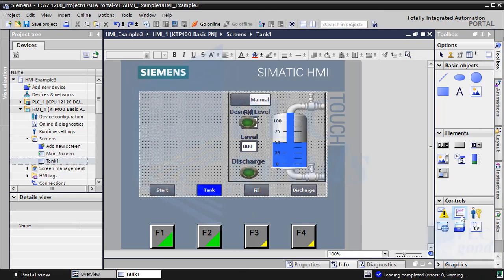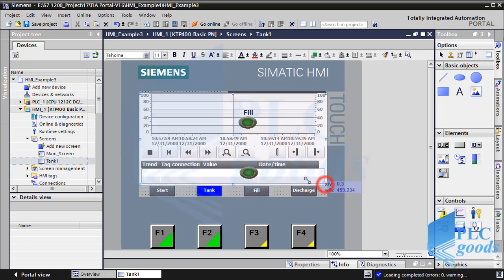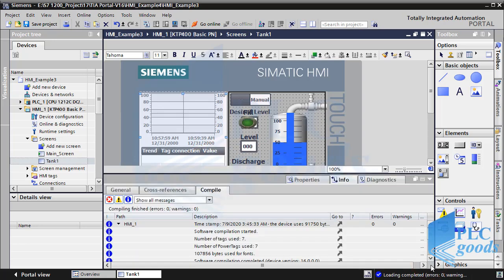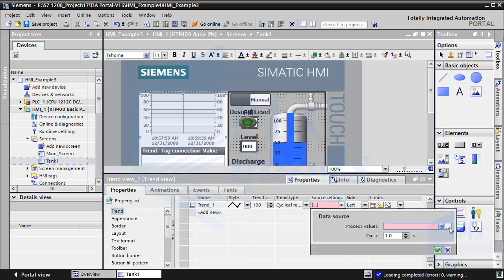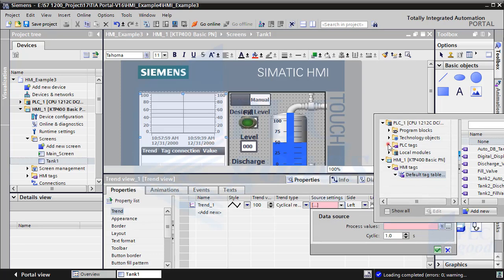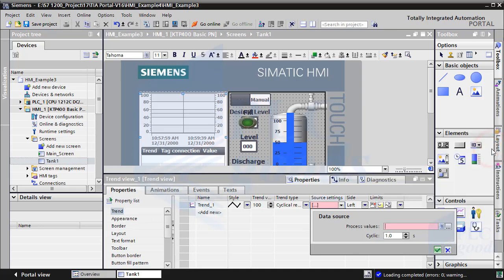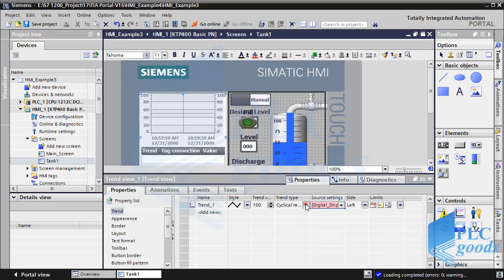Let's start with the screen from the previous video. Let me insert a trend view from the right list. Like other elements, in the properties window we can change its settings. Here we can define new trends. The main part is this column, to determine its connected tag. Let me select the tag which stores the liquid level. The cyclic time is a periodic time which the trend reads and shows the selected tag value. We can also change other settings like its trend data type or its range.